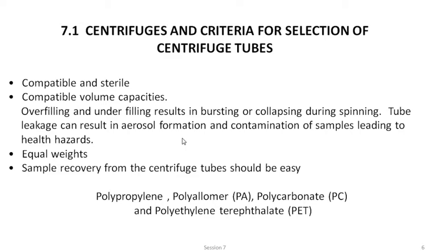You want to precipitate it using centrifugal force. And if it spills and there are aerosols inside the instrument, what will happen is when you carry out the next analysis of another sample, the particular sample which you have already spilled within the instrument will interfere and cause contamination. So you are not supposed to do all such things. Hence, you have to select centrifuge tubes with compatible volume capacities.